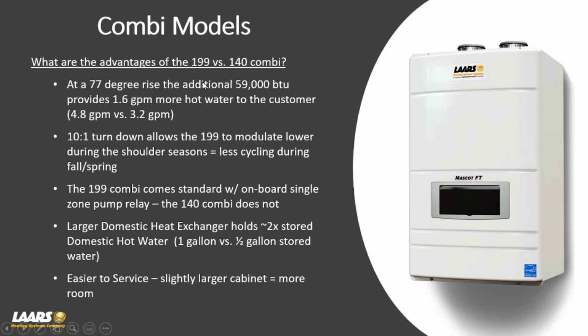Now, also, any of these boilers can be turned down, or derated. So you can drop this down to 50% on a 199, but when you do, you'll actually turn it back to a 5-to-1 turn down.